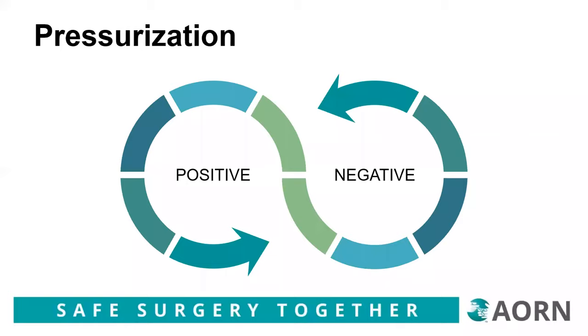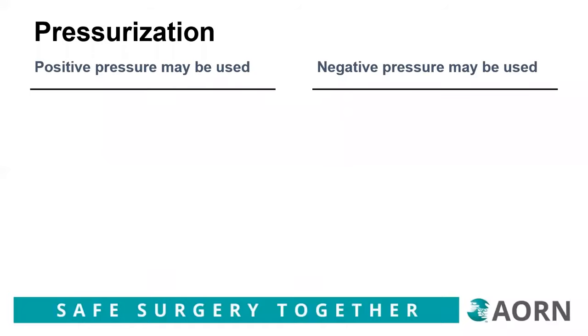One thing these people from maintenance can help you determine is whether altering the pressure to be negative in one or more ORs will have an effect on air balancing in the adjacent areas. This is due to the fact, unknown to many OR personnel, that frequently one air handling system actually provides the air to more than one operating room. So you've got to get your maintenance people into this.